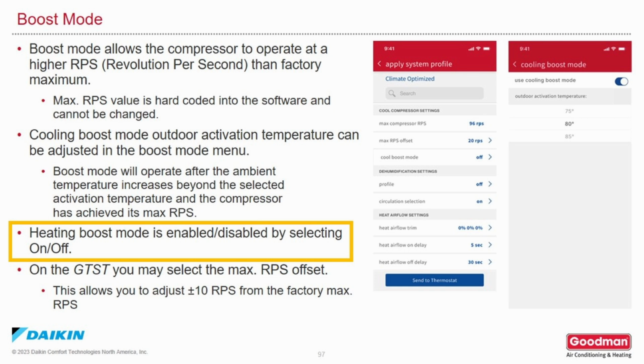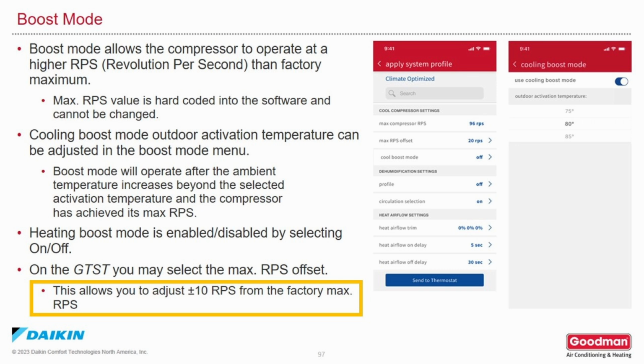Heating boost mode is enabled and disabled by selecting on or off. On the GTST, you may select the maximum revolutions per second offset. This allows you to adjust plus or minus 10 RPS from the factory maximum RPS.